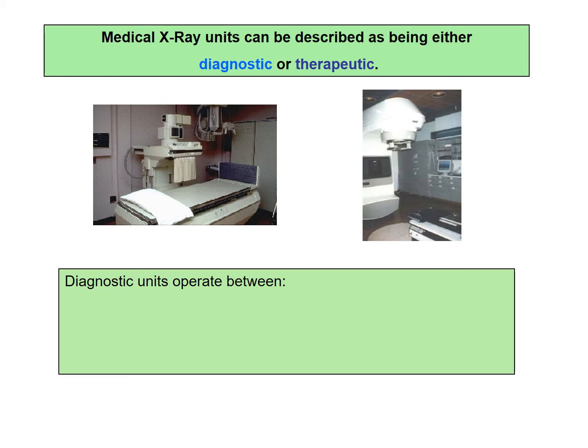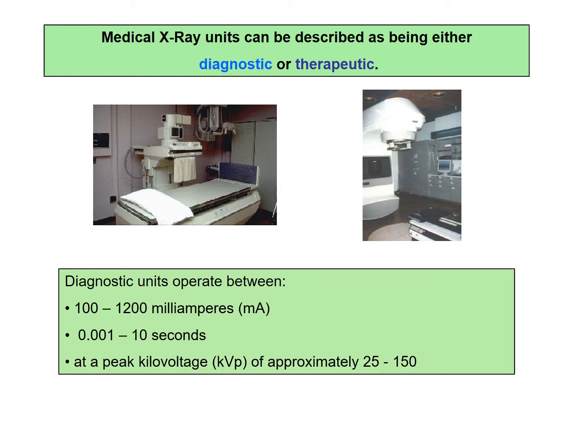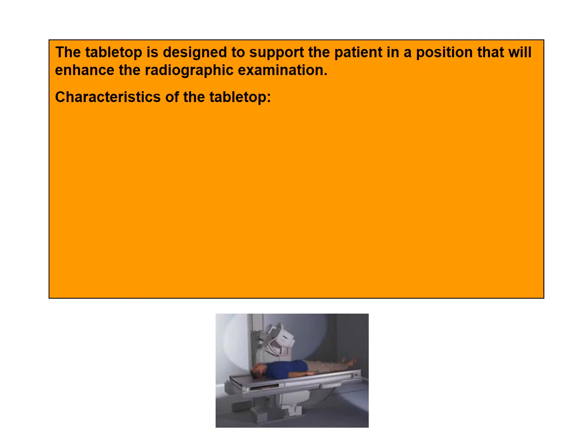In our field we deal with diagnostic units, and we want to keep in mind that diagnostic units operate between 100 to 1200 milliamperes, 0.001 to 10 seconds, and at a peak kilovoltage of about 25 to 150 kVp. Before we move into talking about the tube, we'll talk about some of the external components of the X-ray equipment.